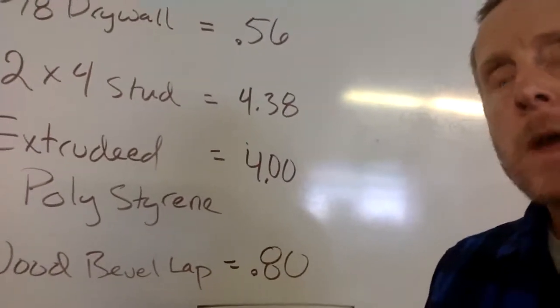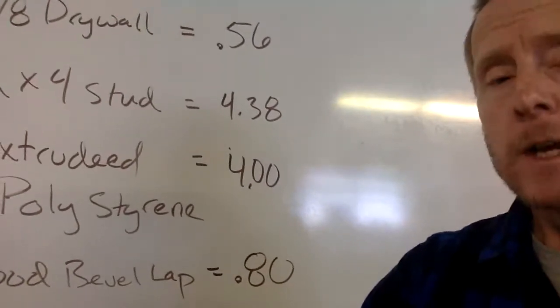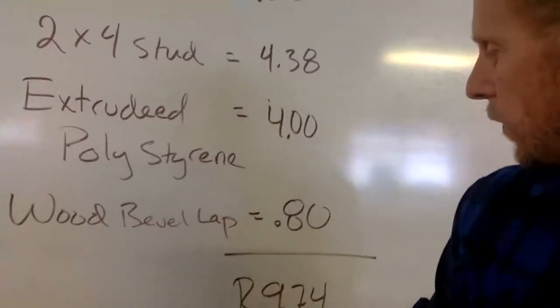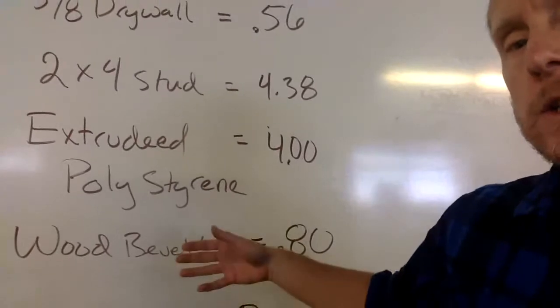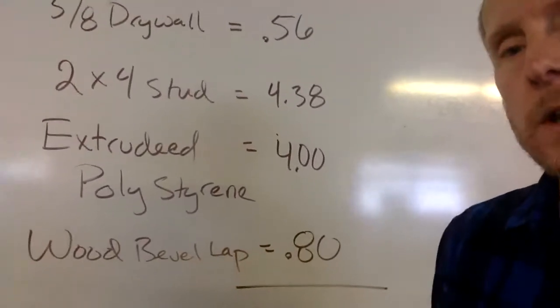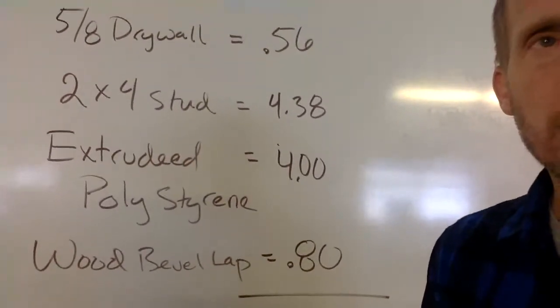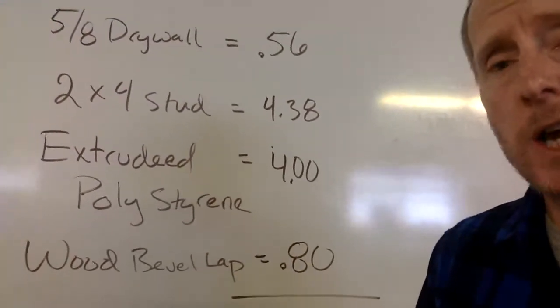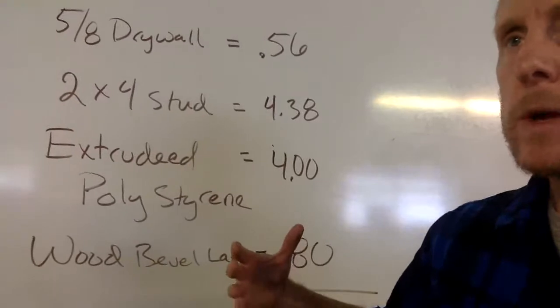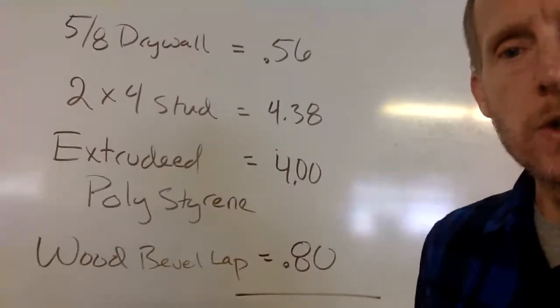So it's lower than through the wall cavity. And what that means is heat will actually flow easier through the stud than it does through the wall cavity itself with the insulated batting. And that's kind of an important thing to think about. You would like to minimize the area or minimize the heat loss through the studs. So maybe we can apply some special insulation to those as well.